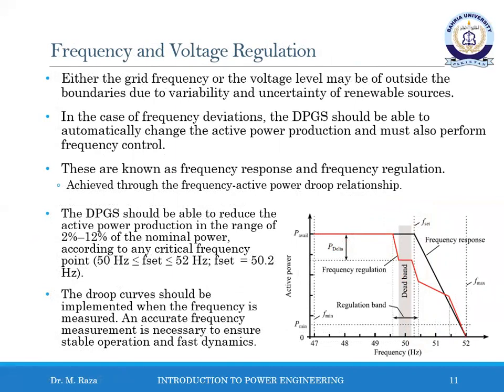Either the grid frequency or the voltage level may be outside the boundaries due to variability and uncertainty of renewable sources. In the case of frequency deviation, the DPGS should be able to automatically change the active power production and must also perform frequency control. These are known as frequency response and frequency regulation, which is achieved through the frequency-active power droop relationship. Then, the Danish grid code requirement of active power reduction by the distributed power generation system with respect to network frequency is illustrated over here.